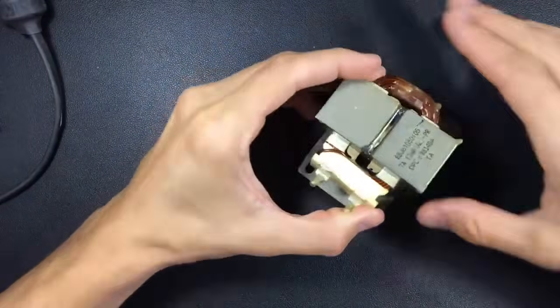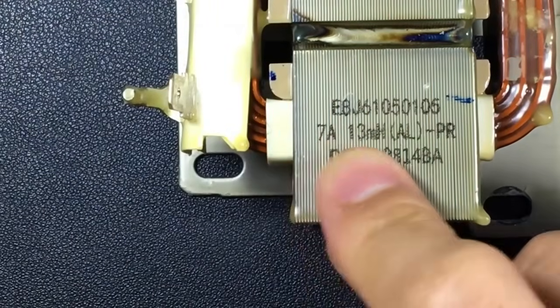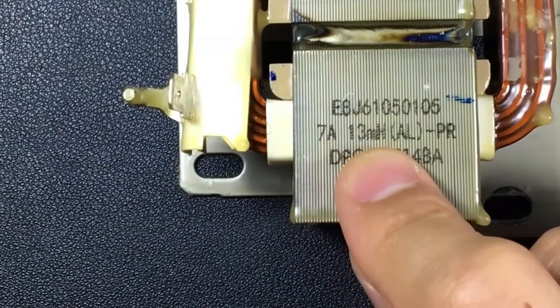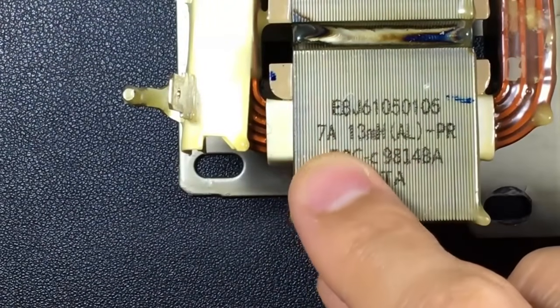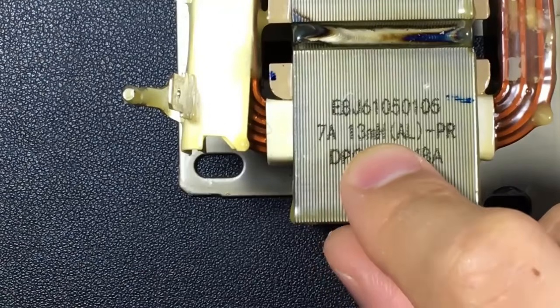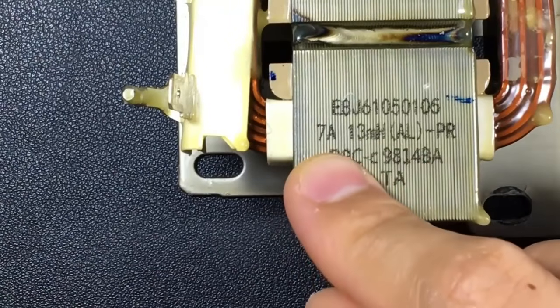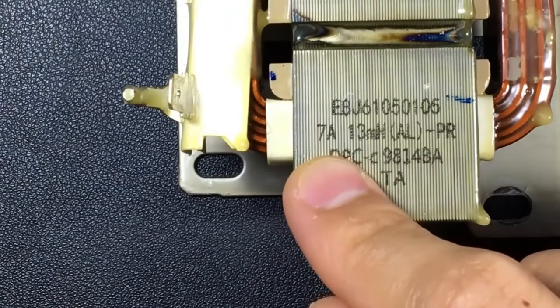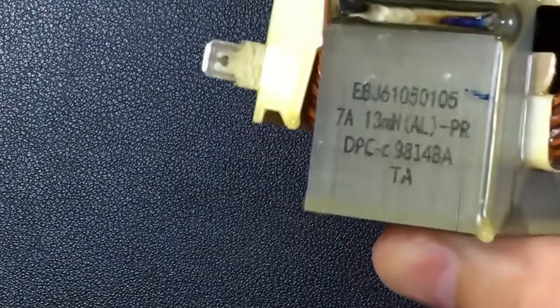In case you have to replace it, the value that you have to see and take into account are the millihenry and the ampere. These are the values to take into account. The millihenry have to be as similar as possible, and the amperage has to be equal or higher. The larger the equipment, the thicker the copper filaments will be.